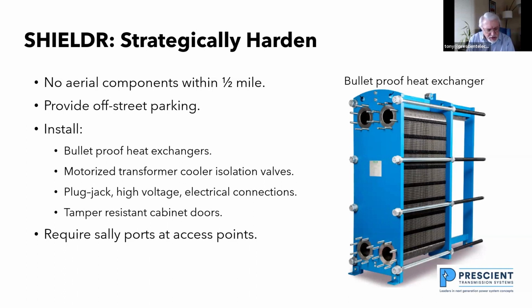On all my components in substations, we should be using plug jack, high voltage electrical connections. We should get away from using transformer bushings and circuit breaker bushings. These plug jack connectors are used wherever I'm building a gas insulated substation. I bring in insulated cables to the substation. I use a plug jack to connect up to the buswork. And I should be putting in tamper resistant cabinet doors. It should be really difficult to open any control cabinet door on any component in a substation unless you have the access keys to get in there.